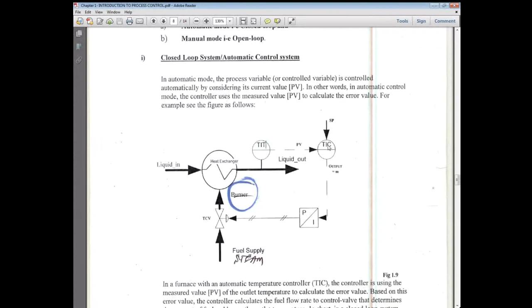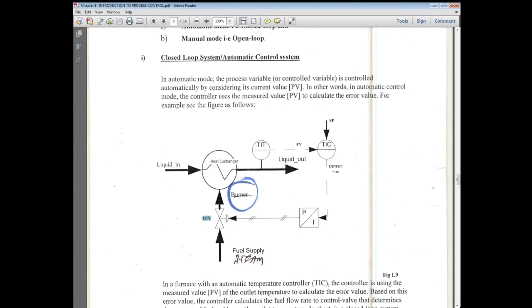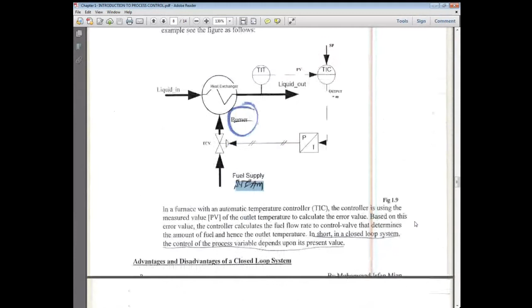See now our notes, right now it is closed loop. The heat exchanger is there, the temperature indicator transmitter is there, it is sending the PV signal to the temperature indicator controller. The output of the controller goes through the I2P converter to this valve, and this valve is controlling the steam. And if we want to make it open loop, we will remove this part or we will put the controller on manual. So it will become open loop. Yeah, I can repeat.